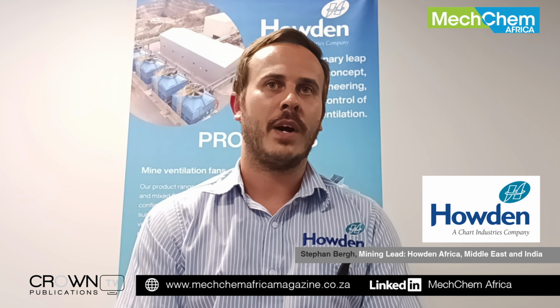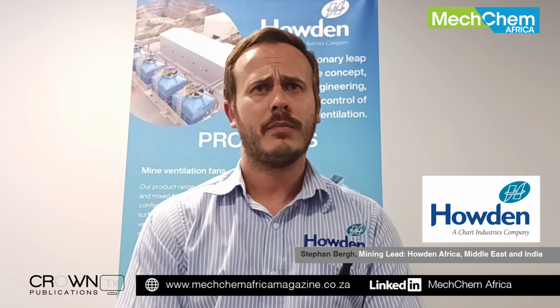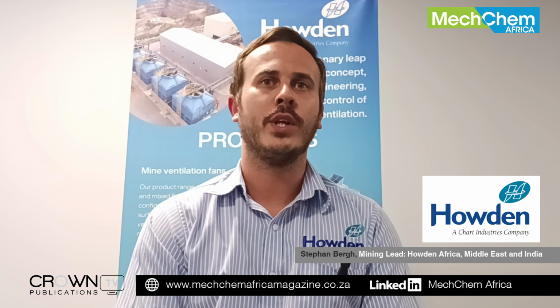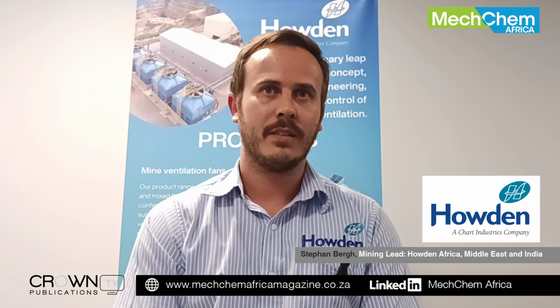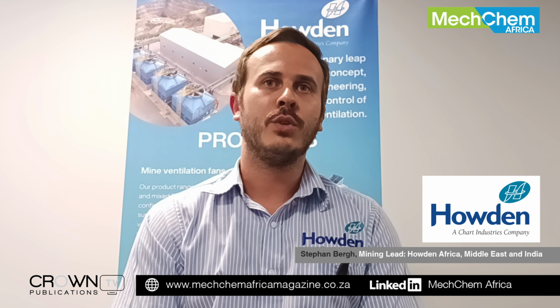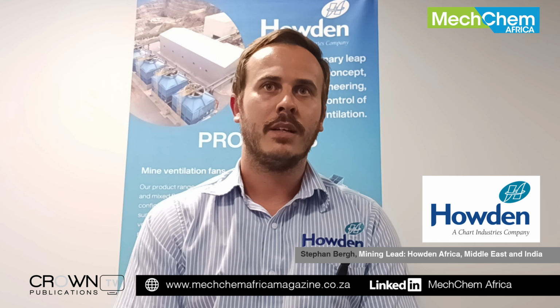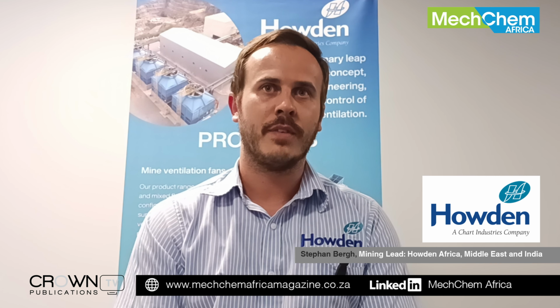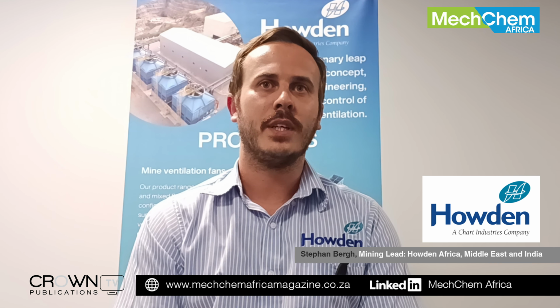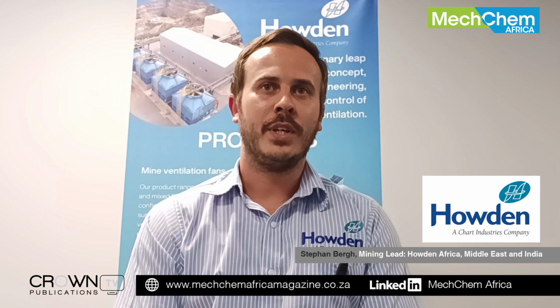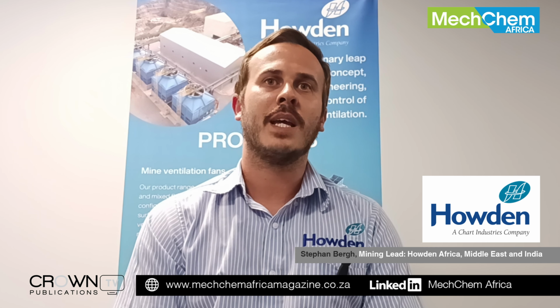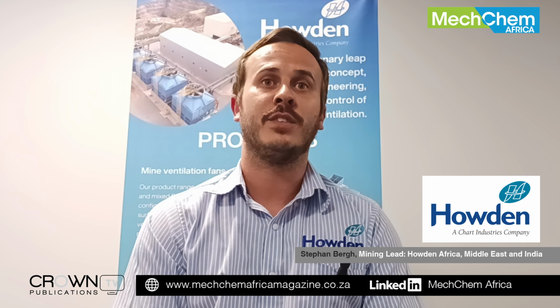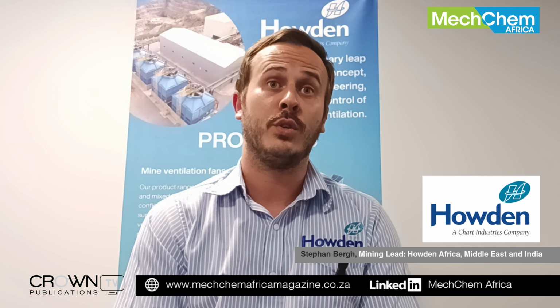And ultimately, level 5 is optimization algorithms. That's where the system looks at the optimal point to run in a 24-hour cycle. It attempts to reduce the system resistance of the mine, looking for the optimal operating point of the fan, essentially reducing fan pressure, reducing fan speed, but delivering the same quantity of air through the mine. So your mine is ventilated, but it uses a lot less power to do so.